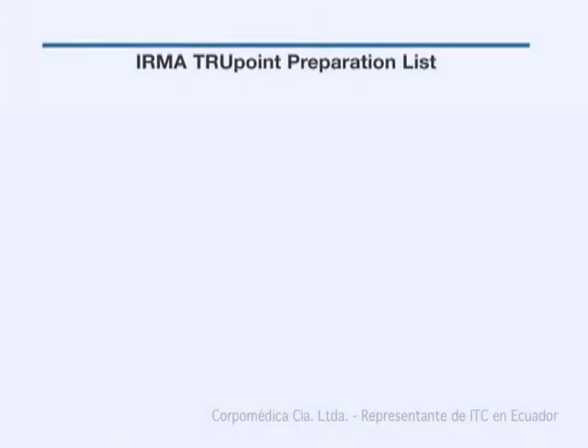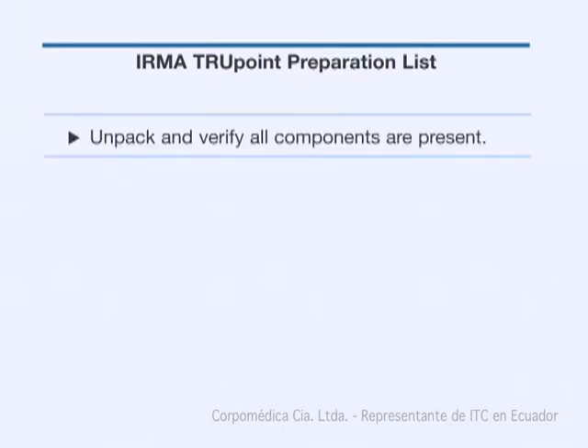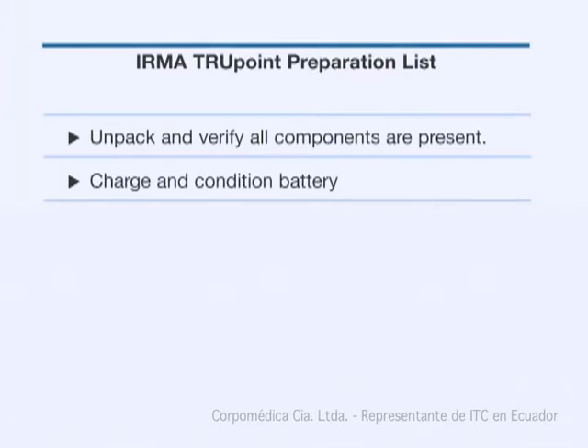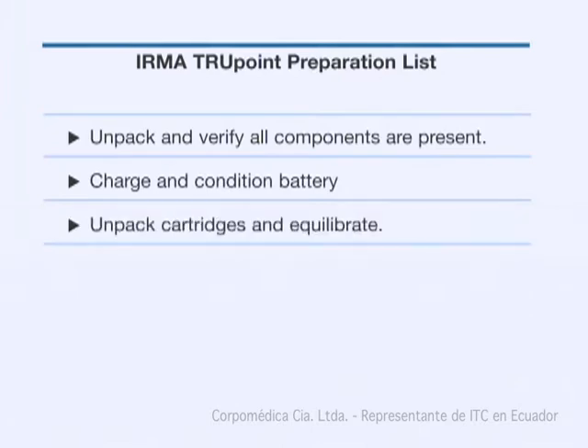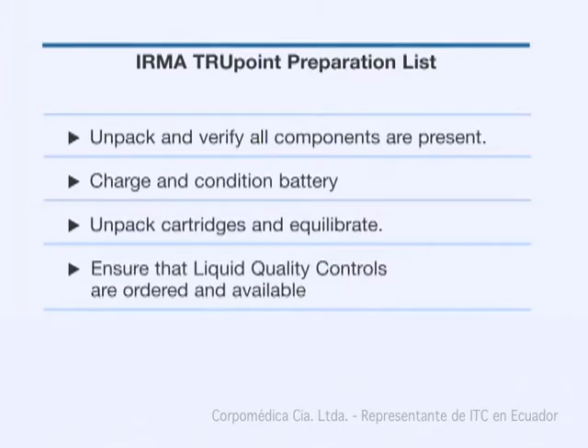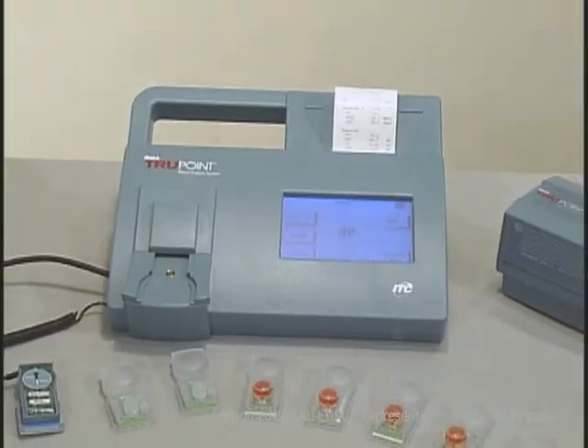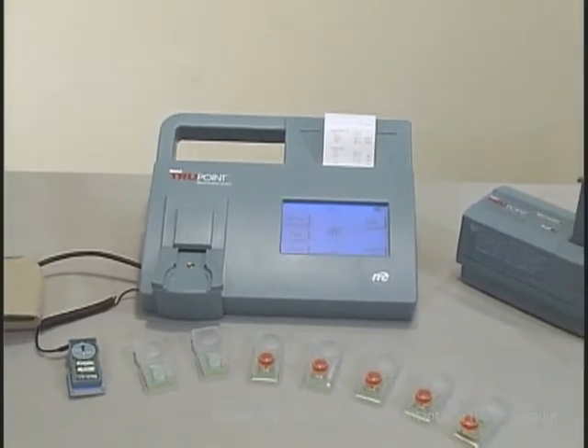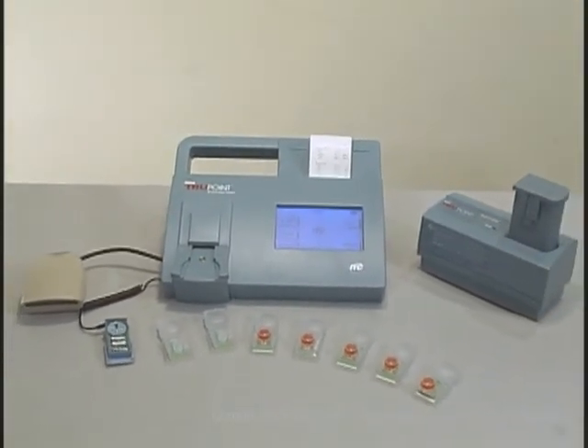Let's review this preparation list before beginning training at your location. Unpack and verify that all components are present. Charge and condition the battery. Unpack the cartridges and equilibrate. Ensure that the liquid quality controls have been ordered and are available. Once you have unpacked your IRMA TruPoint, register it online at www.itcmed.com. The analyzer must equilibrate to the temperature of its operating environment for at least 30 minutes prior to use.